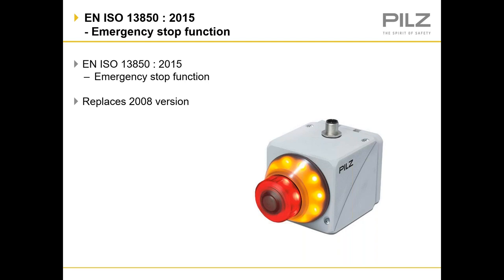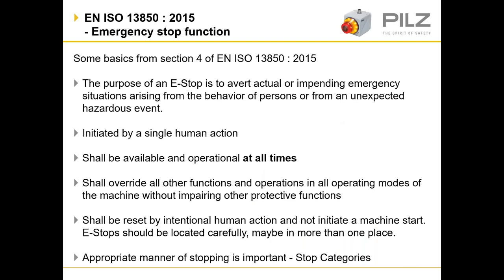This applies if you're building machines or systems. Emergency stops — the king of the stop buttons. Some basics from section 4 of EN ISO 13850: the purpose of an emergency stop is to avert actual or impending emergency situations arising from the behaviour of persons or from an unexpected hazardous event. They should be initiated by a single human action. Emergency stops shall be available and operational at all times — so if you have emergency stops and guard switches in the same series loop, the emergency stop is essentially no longer operational.